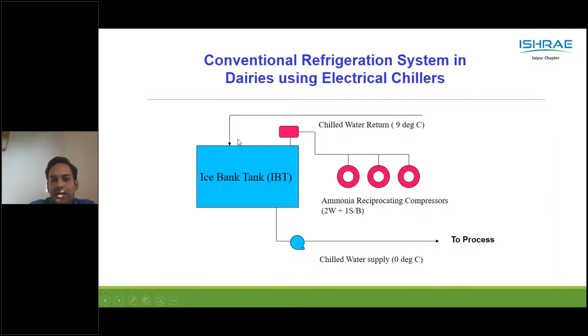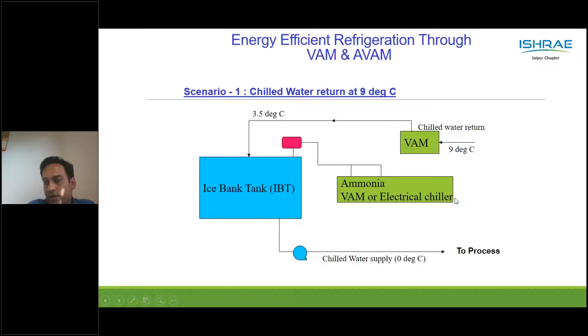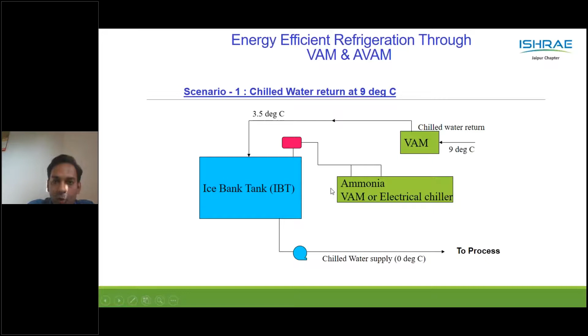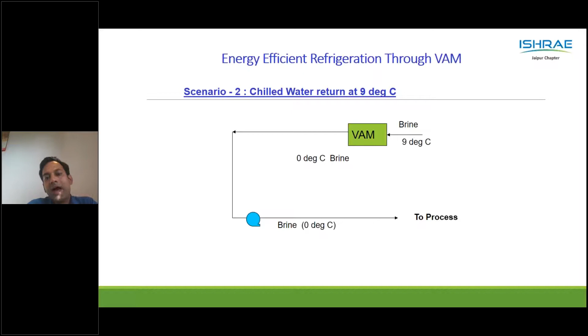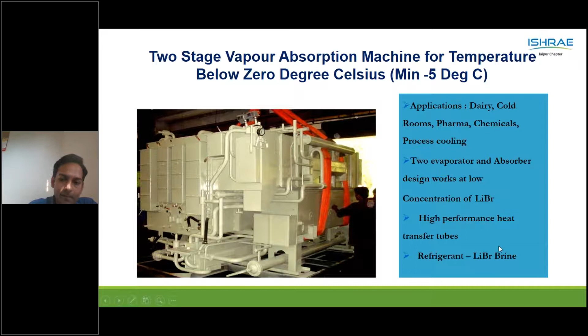In addition to the ammonia machines, VAM can convert up to 3.5 degrees Celsius, and then further conversion from 3.5 to 0. By doing so, the power consumption of your ammonia chiller or electrical chiller will drastically come down, and you can easily take care of the heavy loads in the process plants. Further, in the advancements on vapor absorption machines, VAMs can also directly produce 0 degree brine, which can go to the process. This is a two-stage 0 degree VAM, which can generate up to -5 degrees Celsius, applicable for pharma and chemical. It uses refrigerant, which is lithium bromide brine in it.